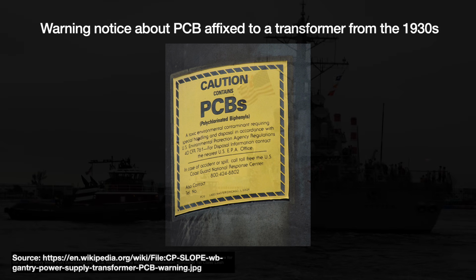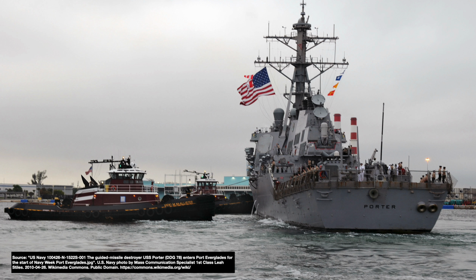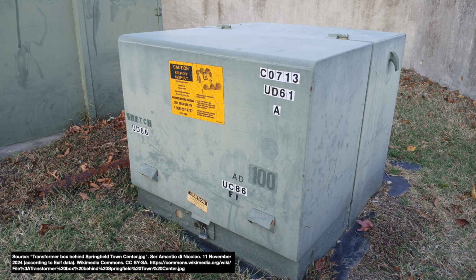Another practical reason involved power savings. This is during the energy crises of the 1970s, and efficiency was the word of the day. When ships berth at port, they take power from the shore, but their power loads were variable and unpredictable depending on task and ship type. While a traditional transformer's nameplate efficiency can reach 98%, that efficiency varies with loading. When loads are variable, you get losses, and the Navy estimated that tens of millions of dollars are lost to distribution inefficiencies, which wasn't ideal.